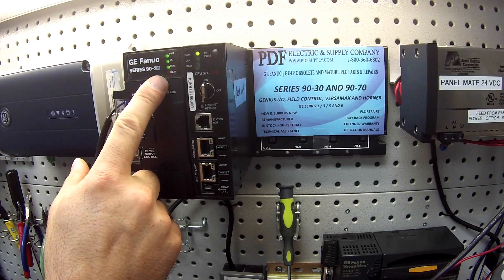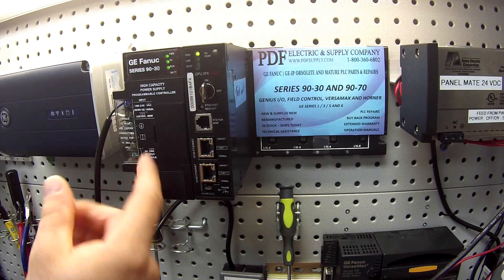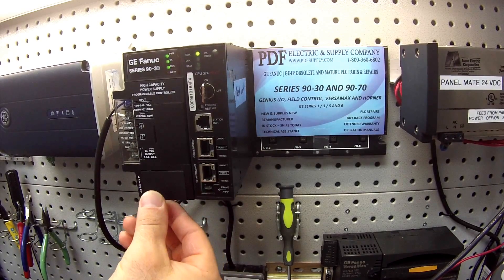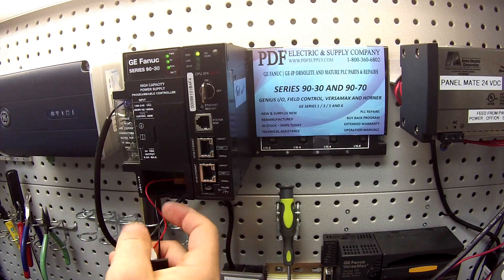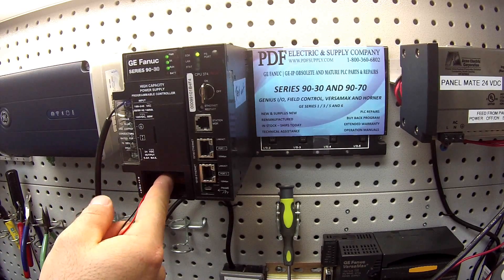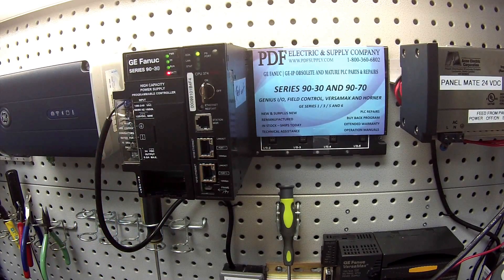The battery LED is red. In the event that the battery is not working anymore, this light will turn red. This door pops open and the battery is located underneath. Here's the battery connected to the power supply — I'm going to remove the battery and you'll watch this red LED pop on. This is a warning: if that red light is on, you don't want to shut this down because it's not being protected.